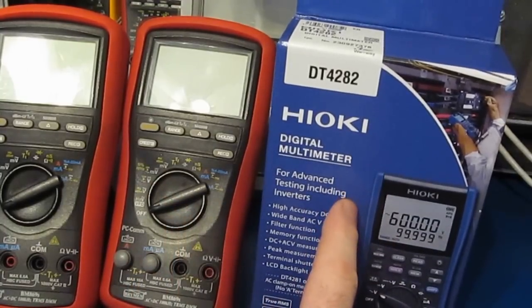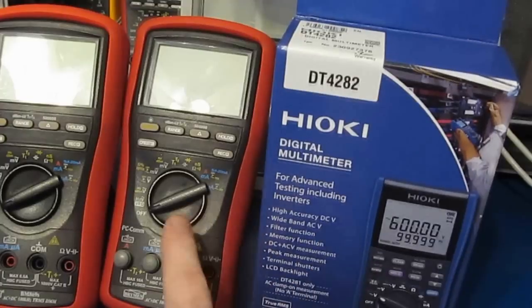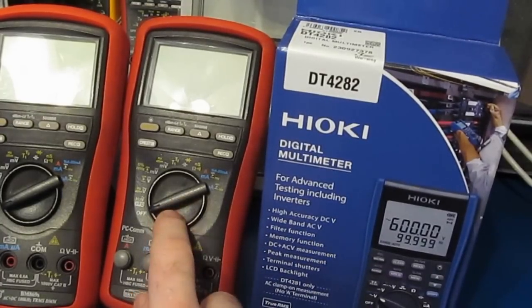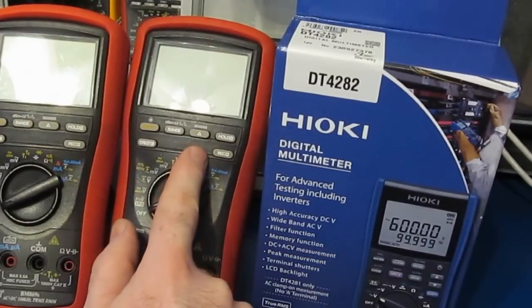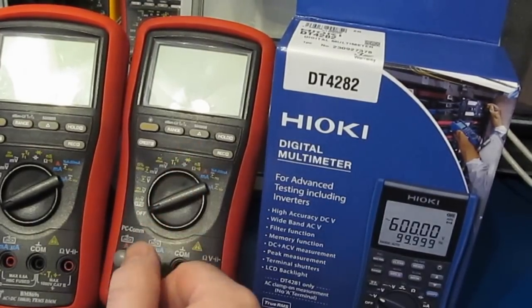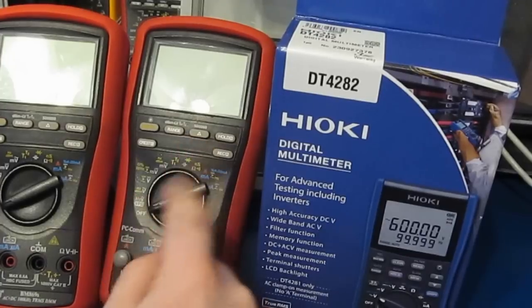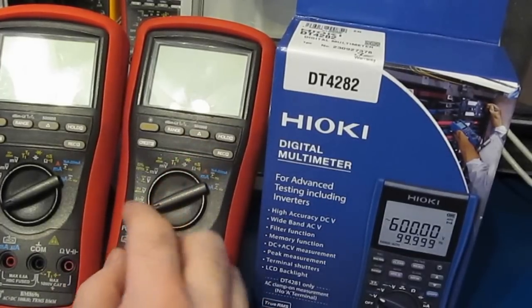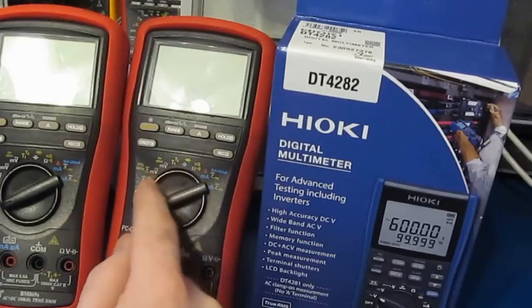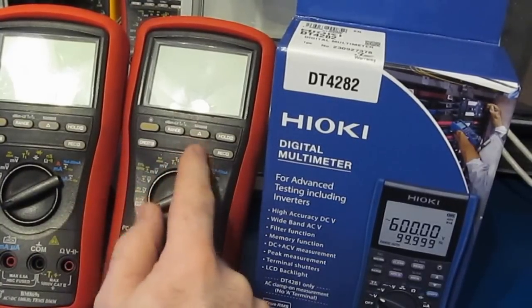The Hioki is a 60,000 count meter, where this Brymen BM869s is a 50,000 count meter, but it has this high resolution mode at 500,000 counts. Now that mode cannot be used for every function, but it does work for the DC volts and the DC microvolts, so ranges that I'm actually interested in.